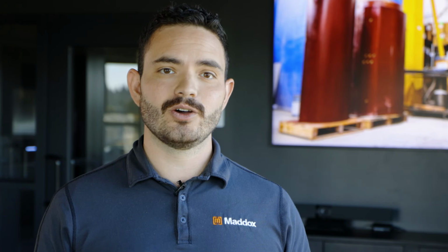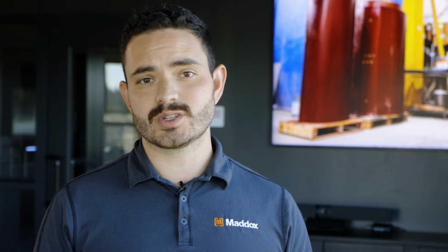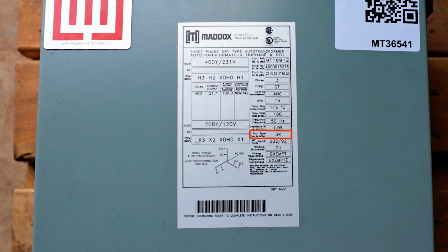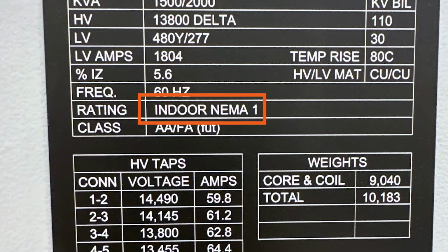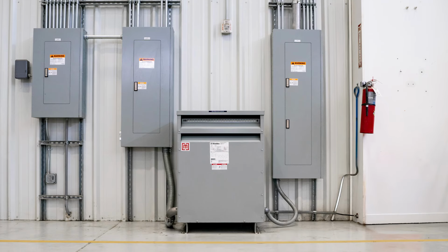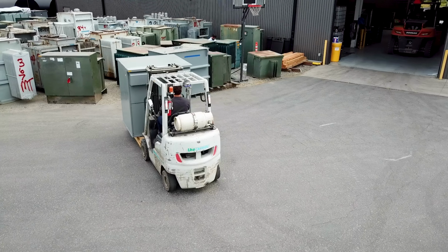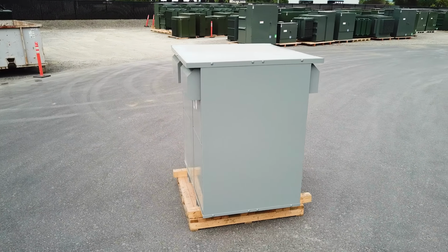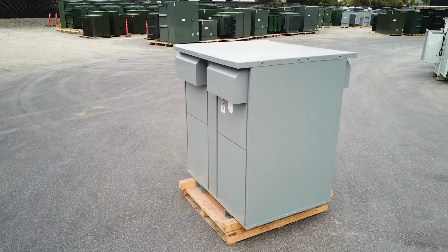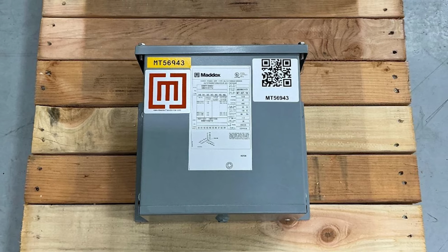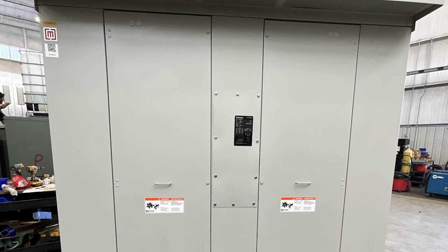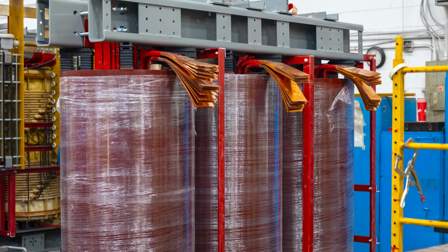Now you may be wondering, when should I get a cast resin unit versus just getting a VPI dry type with a more protective NEMA rating? All dry type transformers have a NEMA rating that indicates the transformer's enclosure level of protection. If your unit is indoors, it probably has a standard NEMA 1 rating. If it's outdoors, it probably has at least a NEMA 3R enclosure with a protective rain shield. Now, NEMA ratings and cast resin epoxy protect different parts of the transformer. NEMA ratings are protection levels for the entire transformer enclosure, while cast resin specifically protects the windings.